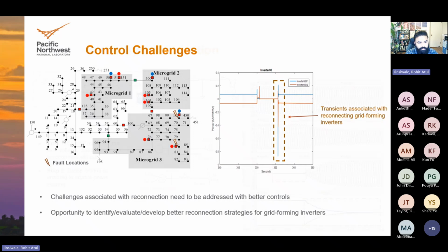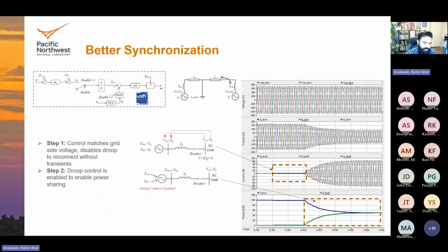This challenge was something the UNIFI Consortium, some of the folks in our lab who work on that, came up with a solution for, which is relatively simple: we close and connect to the system with the droop disabled, matching the voltage but not fully synchronizing or reaching the power set point. Then in step two, once we know we're not creating huge transients, we start moving towards the set point by activating droop. It's a very simple mechanism, but it shows much better transient stability and doesn't create those huge transients on the system.